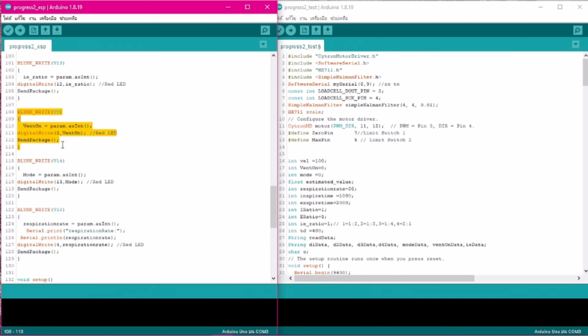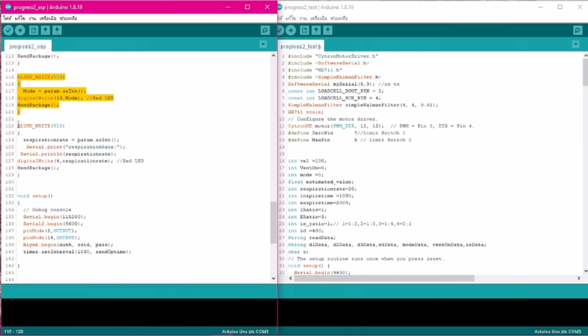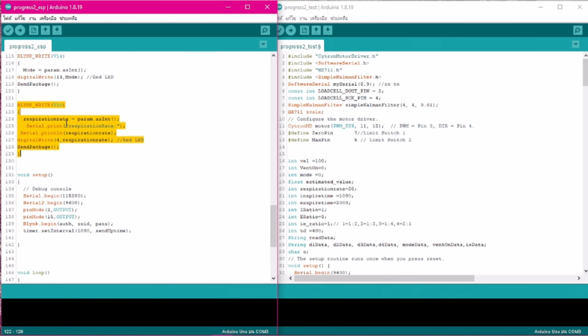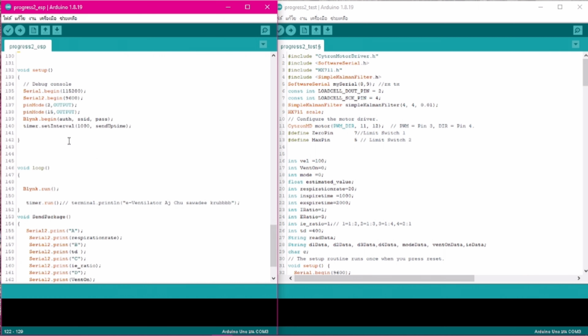This is the function that we use to adjust the mode of the ventilator. If we press the button, it means that we open the assist mode. So this is the function that controls and adjusts the assist mode. And next, this is the function of the mode that controls the on and off of the ventilator. Next, this is the function with which we can adjust the respiratory rate with the slider that we created in the Blynk application. So we can adjust the respiratory rate in our Blynk application.